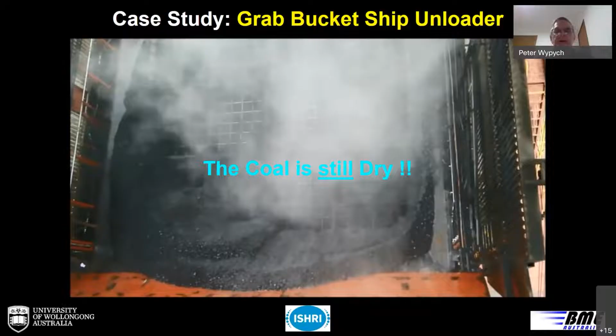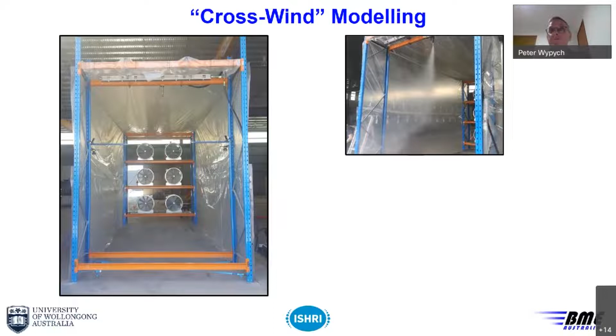Crosswind effects are an issue we came across many years ago, which can upset a lot of otherwise good designs. So we started building a test rig to model and quantify crosswind effects on dust suppression sprays, as you can see here running. We took a lot of data, measuring different nozzles at different pressures, and here we're looking at penetration curves.